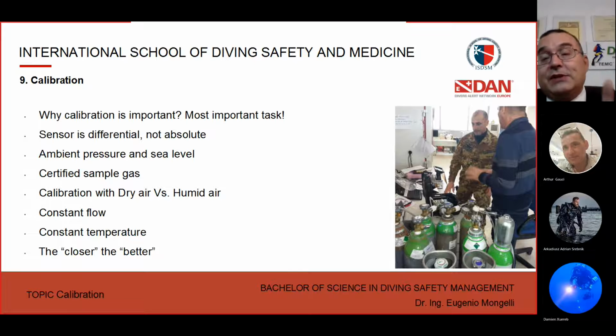We use this gas for recreating the measurement chain that is referable, as we say in metrology, to the international sample. So if you calibrate an analyzer with this kind of certified gas cylinder, you can prove and give confidence in the reading, the error, and the accuracy to the user of the analyzer and to the final customer.